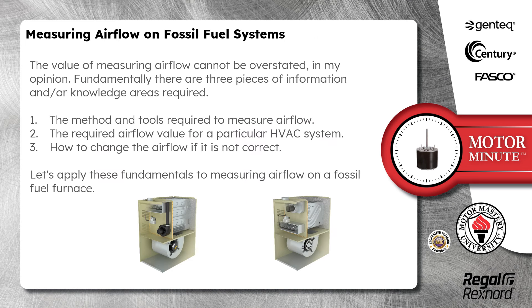The value of measuring airflow cannot be overstated, in my opinion. Fundamentally, there are three pieces of information and/or knowledge areas required: one, the method and tools required to measure airflow; two, the required airflow value for a particular HVAC system; and three, how to change the airflow if it's not correct.